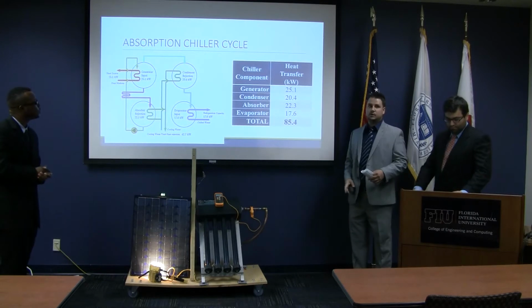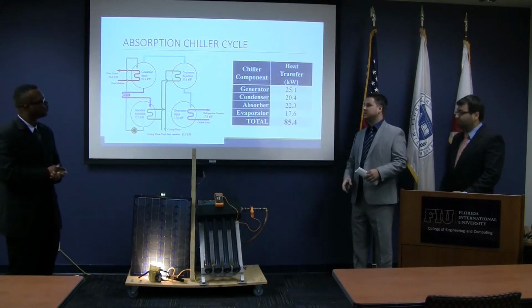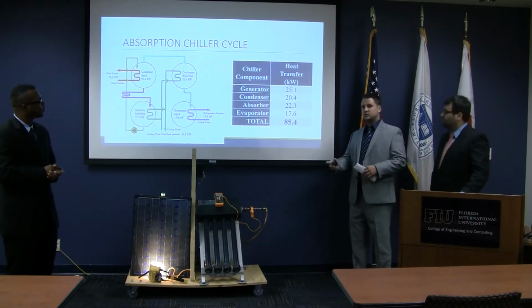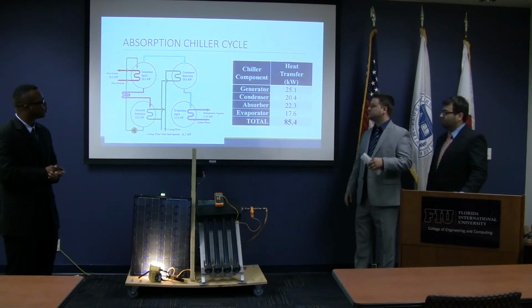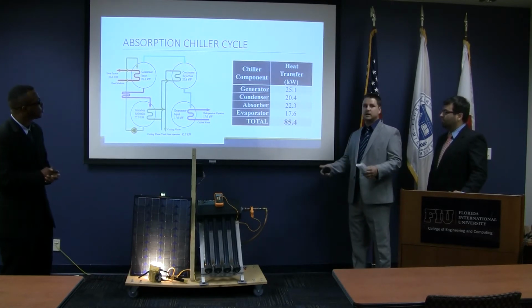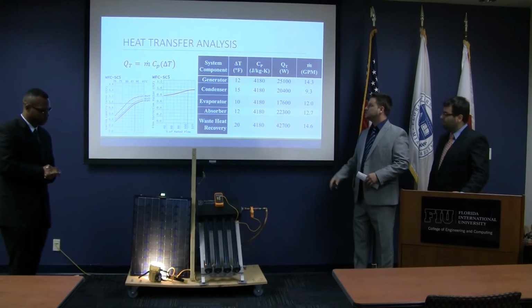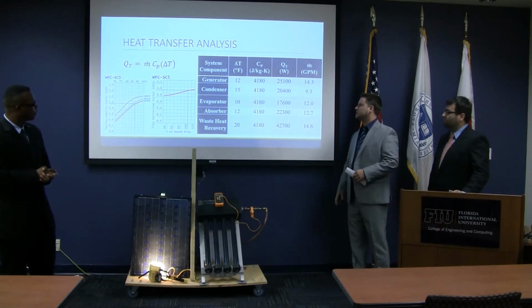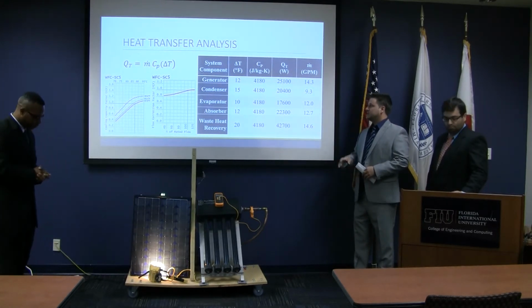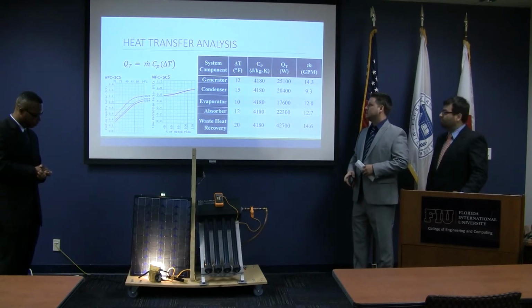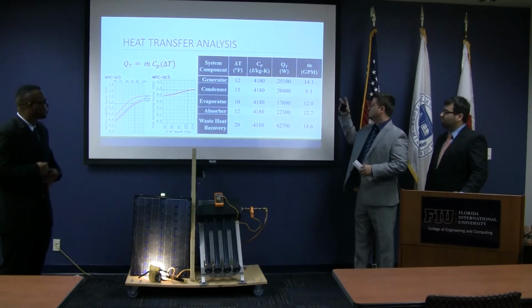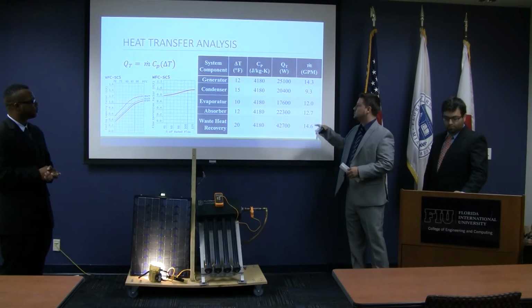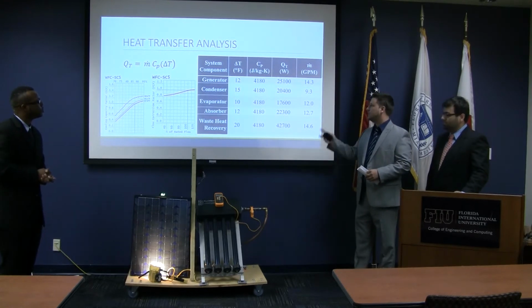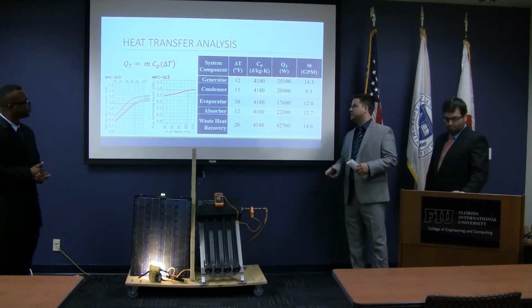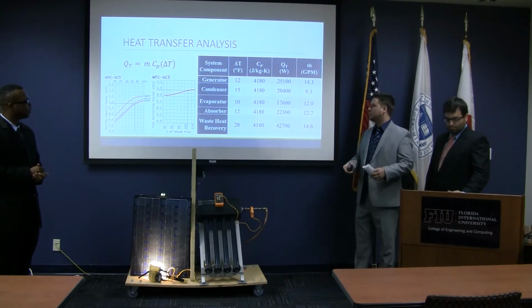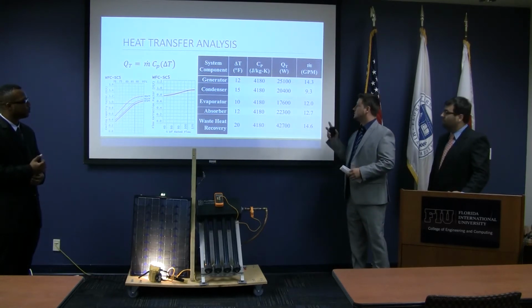When you see the generator only requires 25, we can use a heat exchanger, absorb that heat, and preheat the water from the solar water heating system and make it easier on that. So in choosing the water-fired chiller, we had to do a heat transfer analysis, which is standard engineering calculations. We assumed mass flow rates given by it, also the heat input by all the components, which you saw before. The delta T, which we can achieve by slowing down or speeding up the water, we will choose pumps that'll be able to satisfy that.